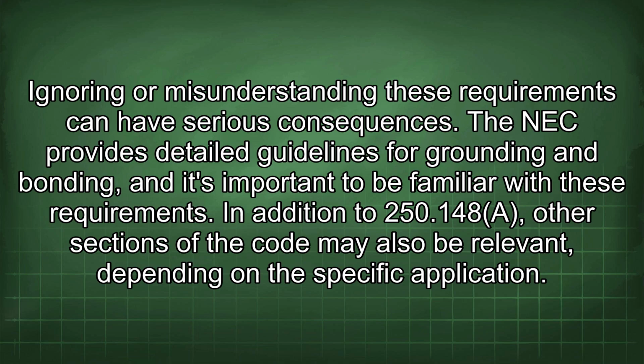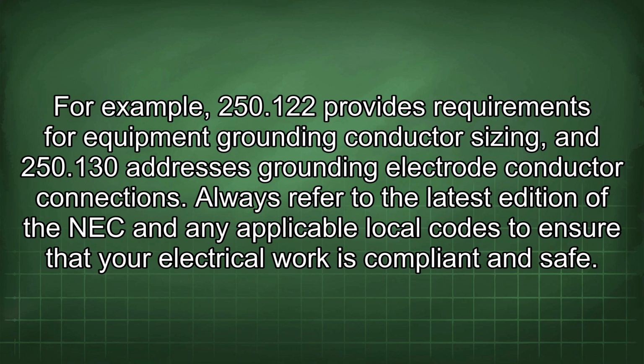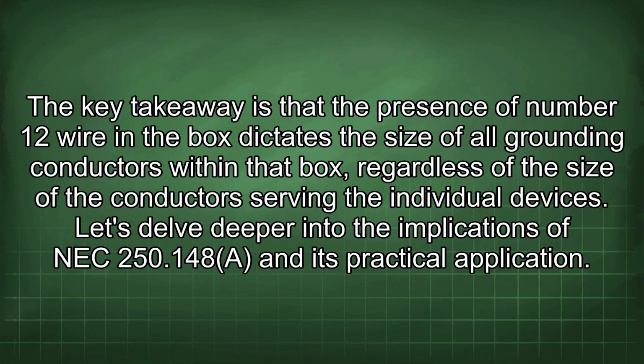In addition to 250.148a, other sections of the code may also be relevant, depending on the specific application. For example, 250.122 provides requirements for equipment grounding conductor sizing, and 250.130 addresses grounding electrode conductor connections. Always refer to the latest edition of the NEC and any applicable local codes to ensure that your electrical work is compliant and safe. The key takeaway is that the presence of number 12 wire in the box dictates the size of all grounding conductors within that box, regardless of the size of the conductor serving the individual devices.